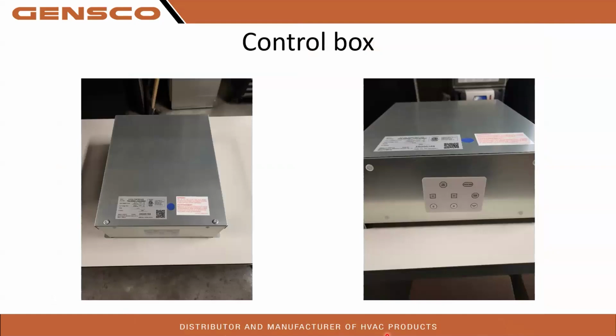It also comes with your control box. So this is mounted in, or comes in, the coil box. You don't have to buy this separately. It comes with it. This is the brains of the operation. It does all the communication between the heat pump and the coil, and also between the coil and the furnace. So it transfers all the 24-volt controls to DC communication back and forth. On the outside of it, it also has this little operation panel. So if you can, make sure that's faced out so it's easily accessible and people can see it on a normal basis. We'll get into that a little bit more.